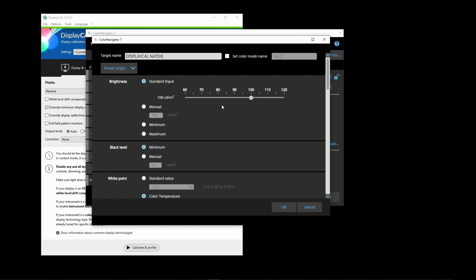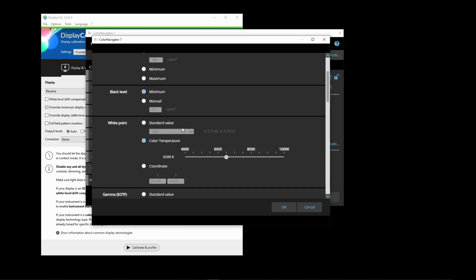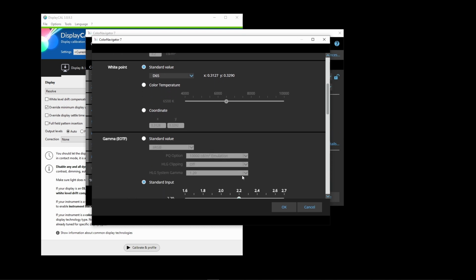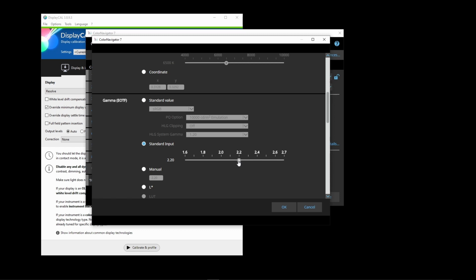We've got 100 nits as our standard luminance level, and black level is always at minimum. The color temperature you can choose from the slider, but it's easier to just select D65, and you can see the chromaticity points for D65 there. For the gamma, we're going to choose a standard gamma curve of 2.4.